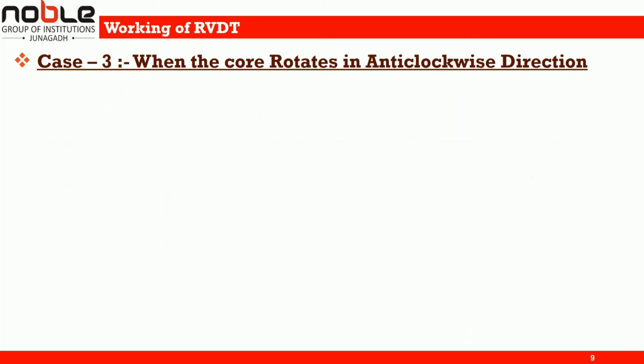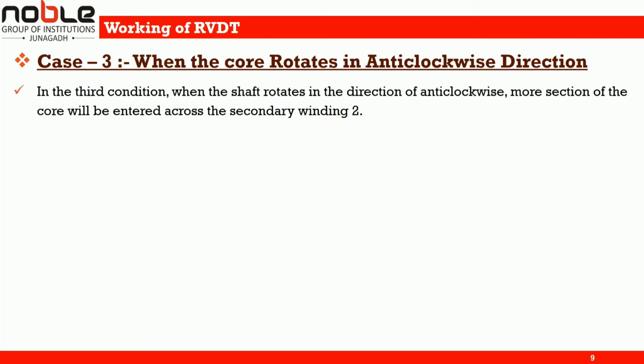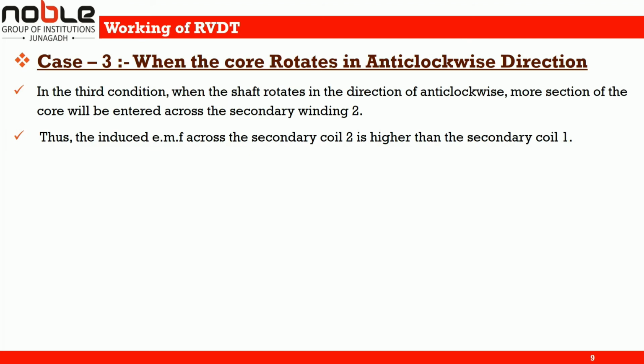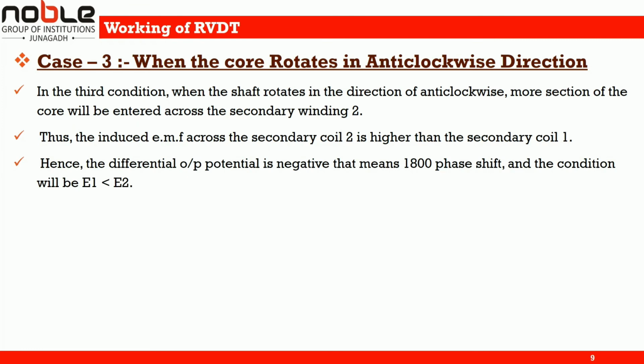Now, in case number 3, when the core rotates in anti-clockwise direction. In the third condition, when the shaft rotates in the anti-clockwise direction, more of the core section will enter across secondary winding 2. Thus, the induced EMF across secondary coil 2 is higher than secondary coil 1. Hence, the differential output potential is negative. That means a 180-degree phase shift, and the condition will be E1 less than E2. So E0 is equal to E1 minus E2. Here E1 is less than E2, so we can say that E0 is negative.